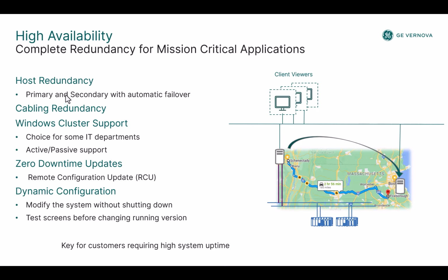So we support host redundancy with the primary and secondary. There's cabling redundancy support between different PLCs in case one connection or network goes down. We support clustering. We also have zero downtime updates using redundancy, where we can automatically switch operations to the secondary while we do project configuration updates and automatically synchronize those for you, as well as the ability to do a number of operations in a dynamic way so that as you make those changes, they're propagated to the system while it is running.